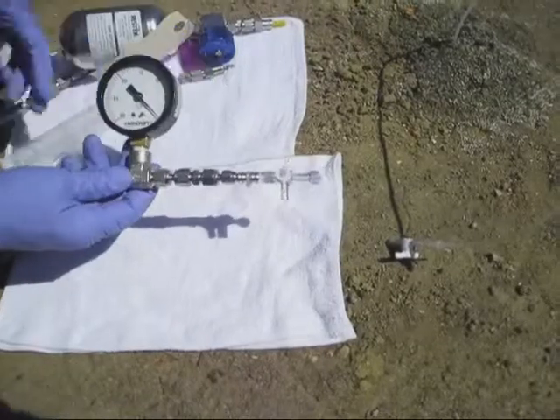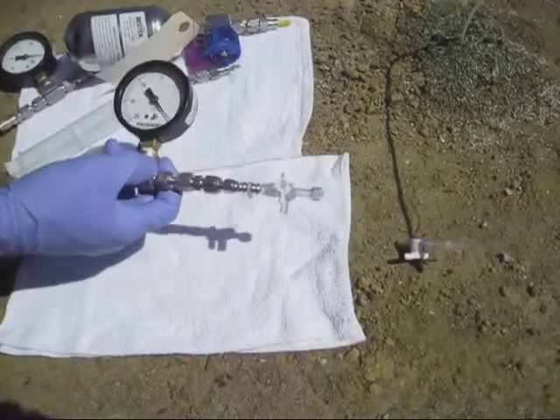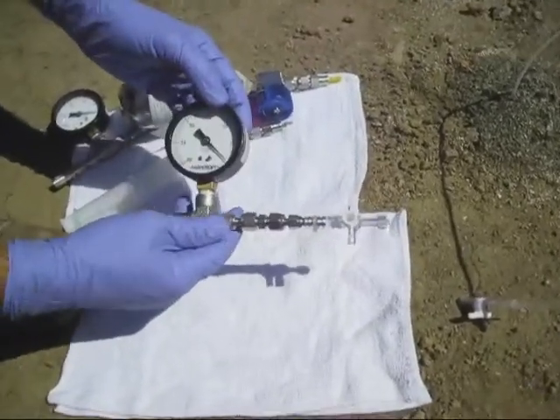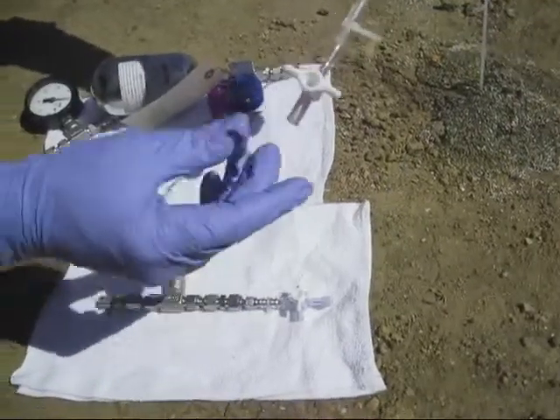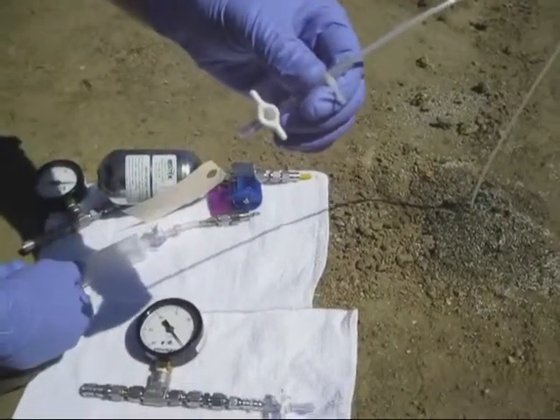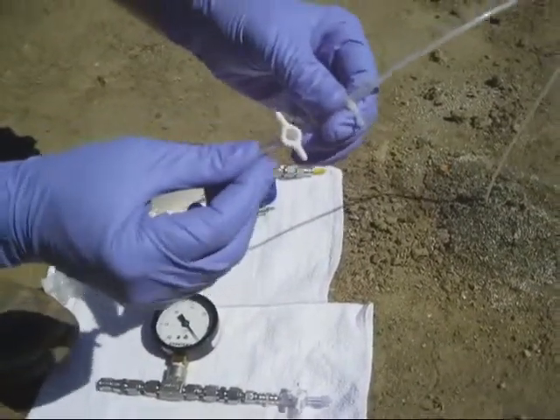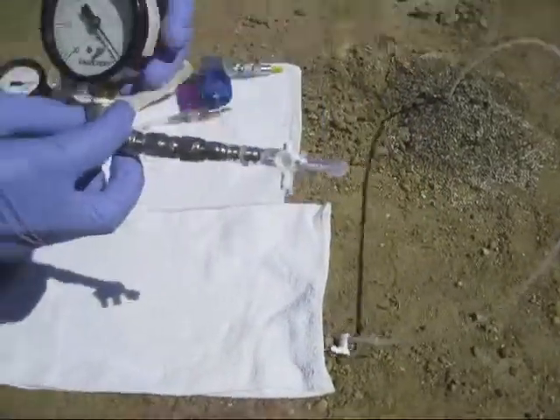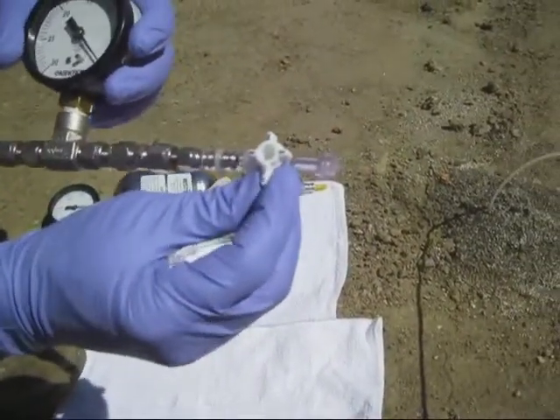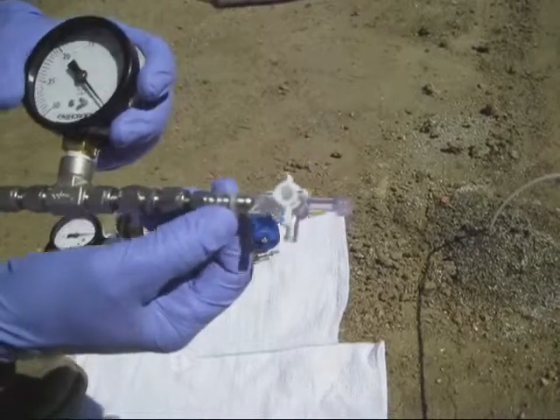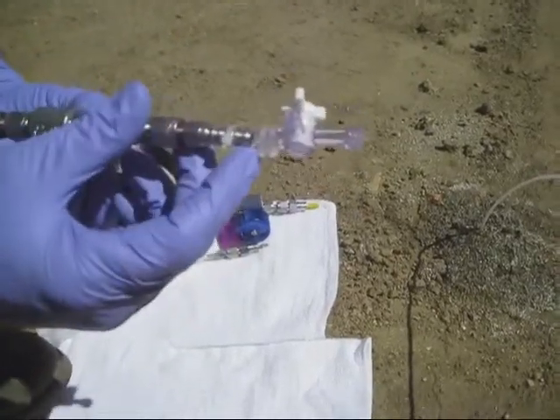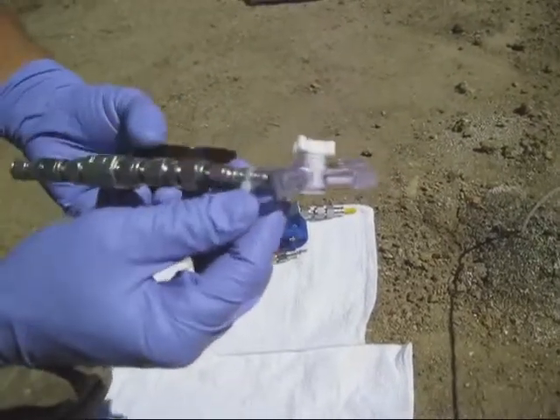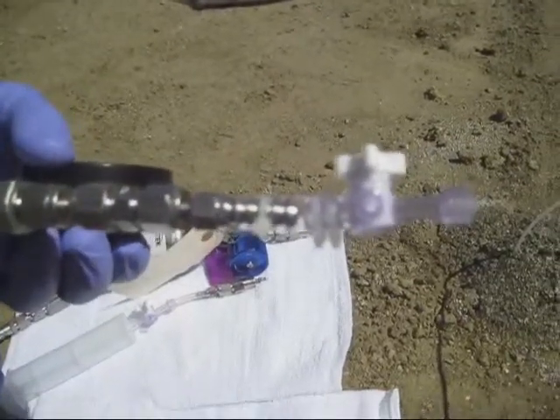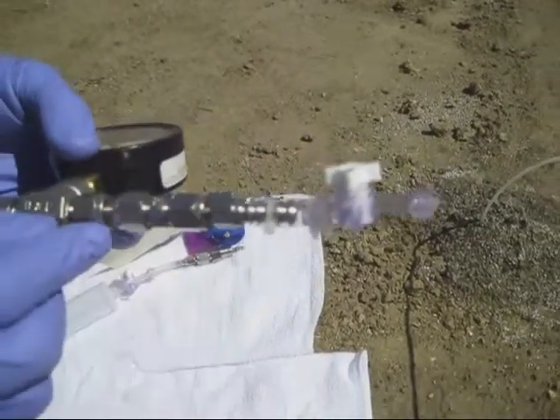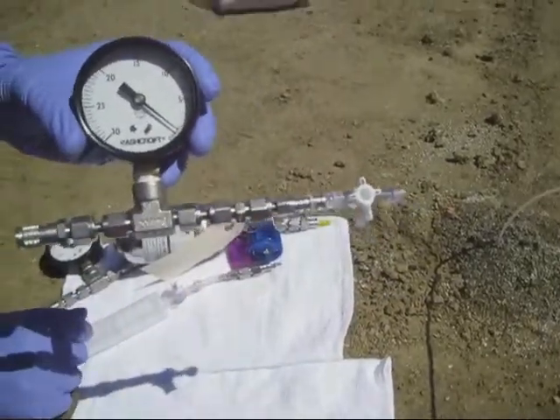Before we begin sampling, I'm going to connect my sample assembly up to our probe. The probe we have here has a Luer lock on-off valve with the Luer lock connection, and I have connected a three-way valve onto the barbed end of the sample assembly. I've used a piece of Tygon connector tubing to make that connection, and I've tightly zip-tied these connections to make sure they're airtight. We're going to test all these fittings right now by doing what's called a shut-in test.